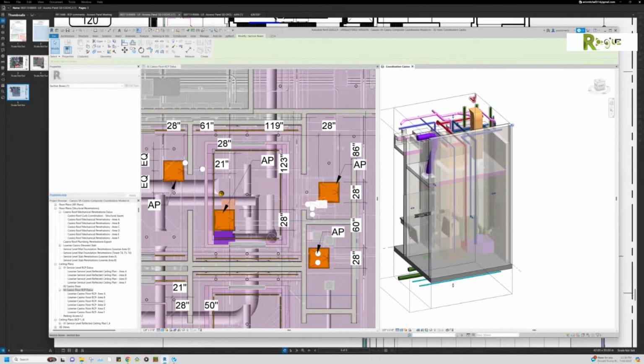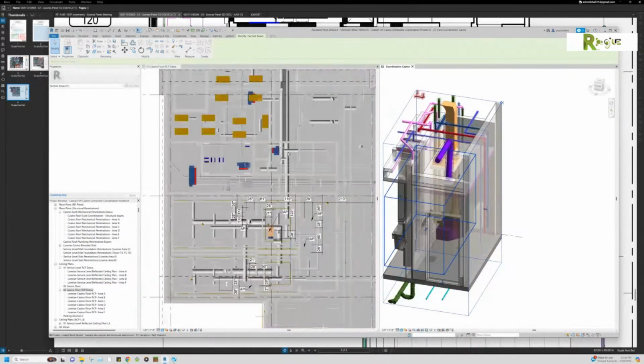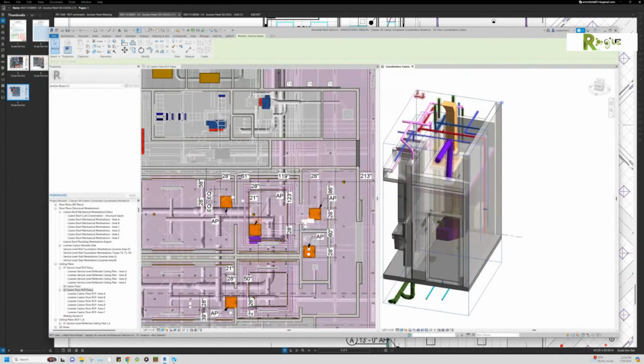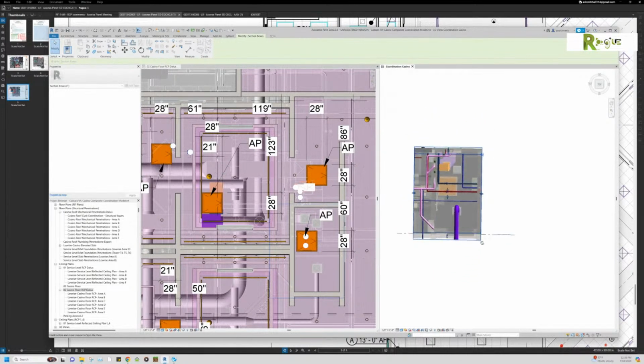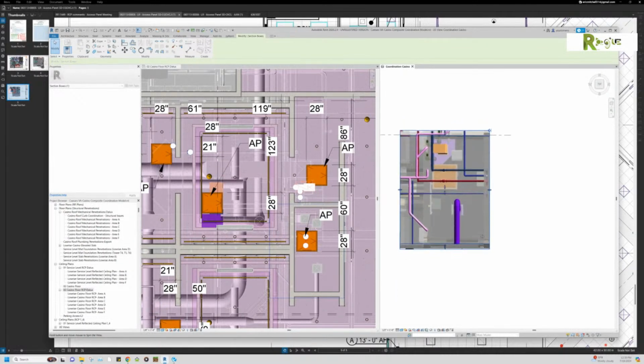No lights in the room. The electrical lights don't match the architectural lights. It's funny when the note says align with the lights. It's a fool's errand. And unfortunately, so just push. Do you want me to center this one out? You know what I'd probably do with that one? Don't really have a light in the center, do you? If we move this, we're going to move it to where the light's going to be. They're going to put a wall sconce in here. Yeah, that's exactly right. Remember, it's an EVS. So let's move on.